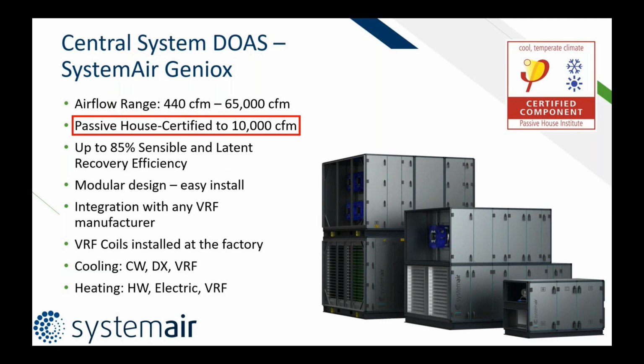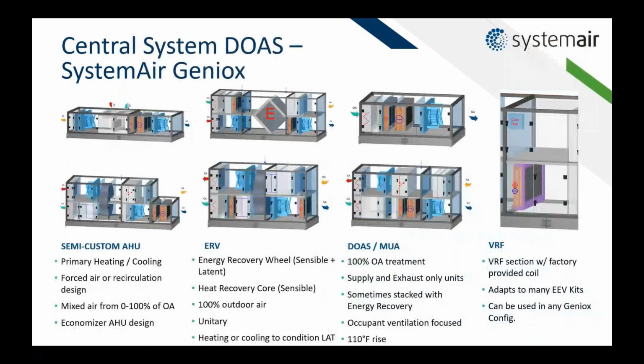Those VRF coils are installed in the factory. The cooling options here would be chilled water, DX, or VRF. And then with heating, you can do hot water, electric, again, or VRF. What do you do for frost control? Well, you could do preheat, you could do timed exhaust, you could do a modulating wheel. We can handle frost control, no problem. So, central system. Like I said, this is a very modular unit. I'm just showing some other options here. It's a semi-custom AHU. There are a lot of different options available.